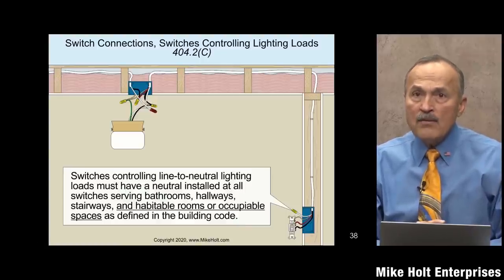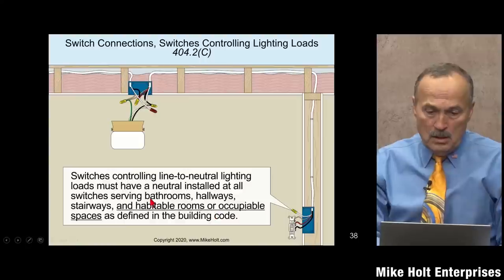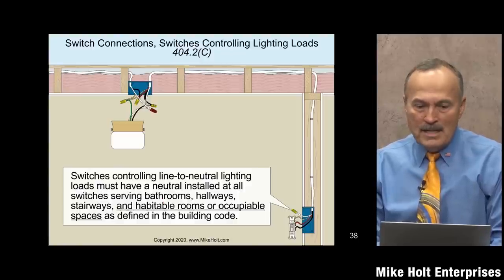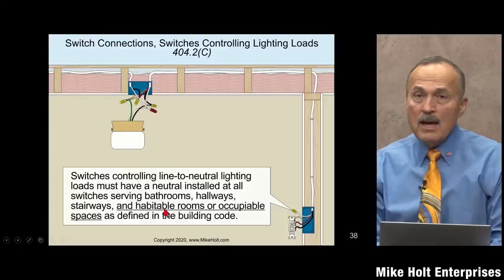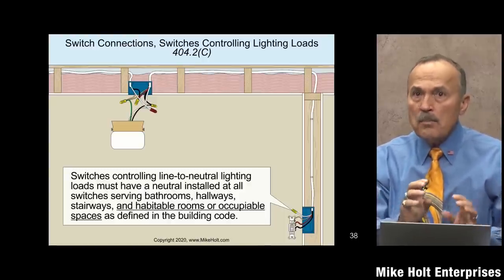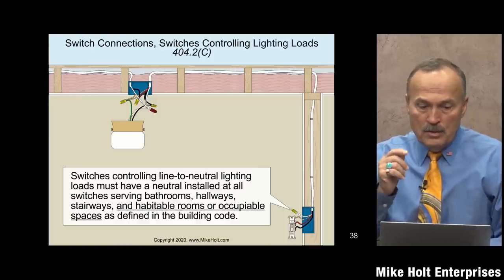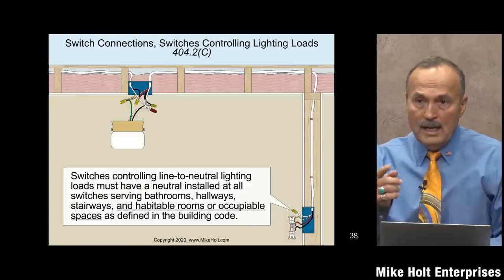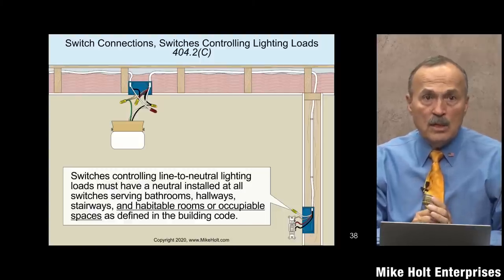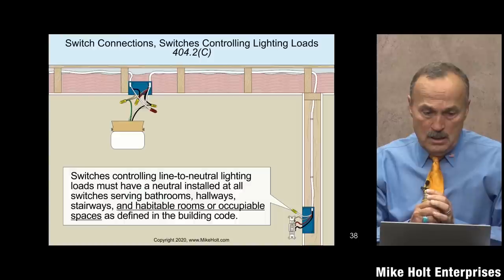So in a dwelling unit, it looks like you have to have a neutral at every single switch location in those listed spaces. There are places where you don't need a neutral — for example, switches for outside lighting, garage lights, unfinished basements, attic spaces, and closets do not require a neutral.